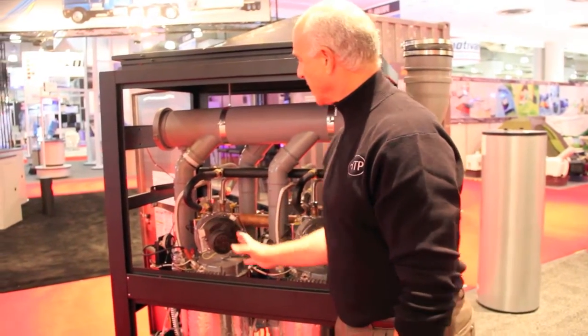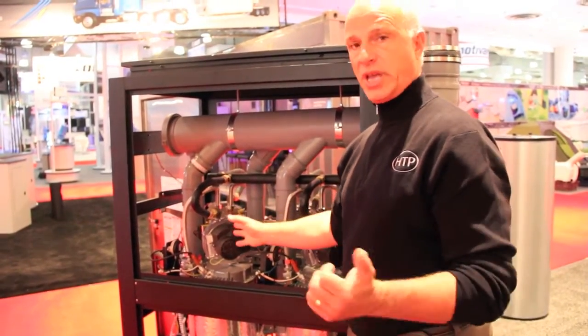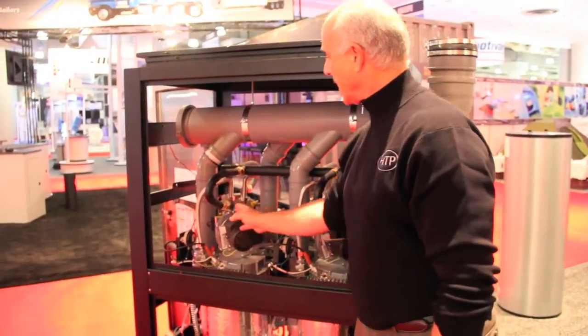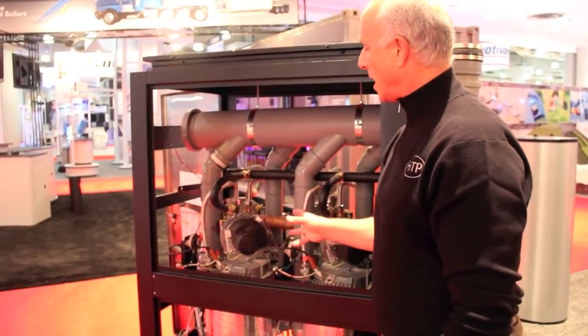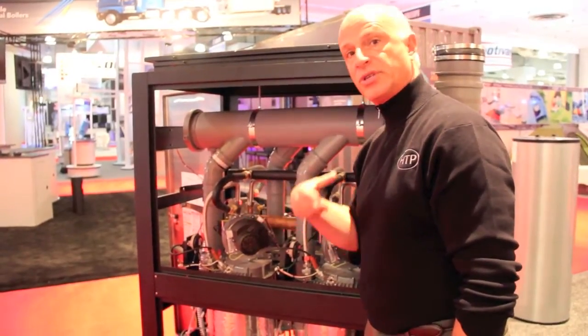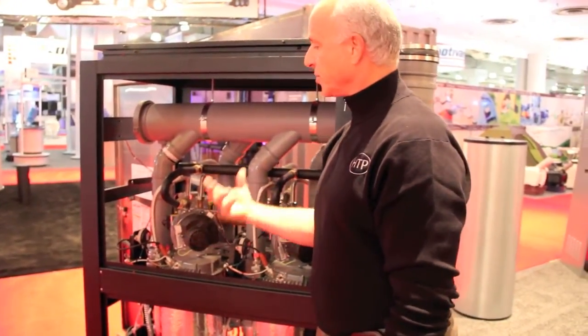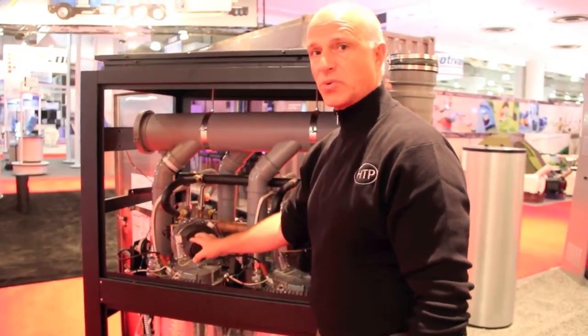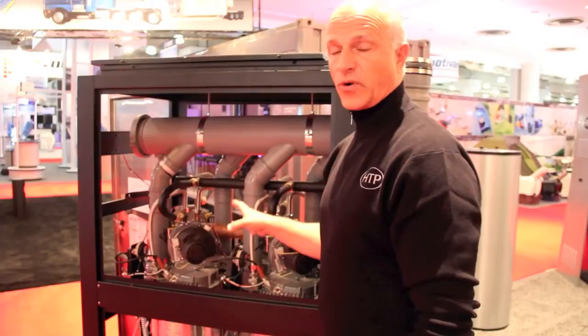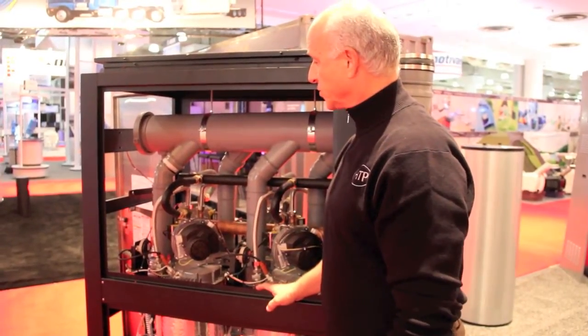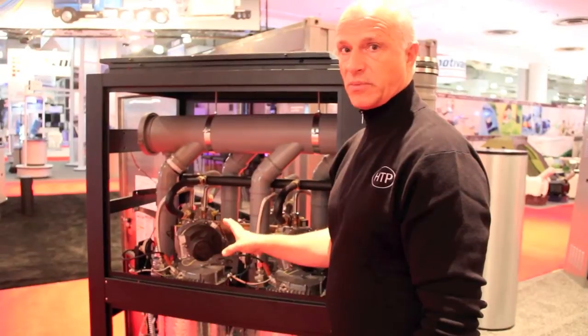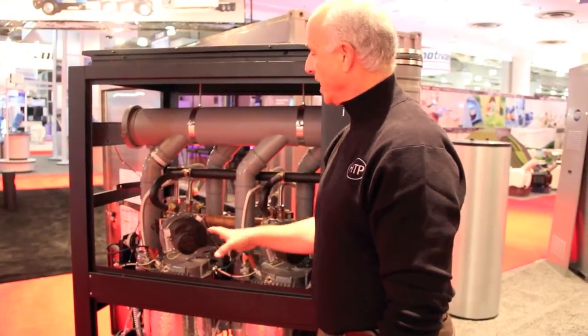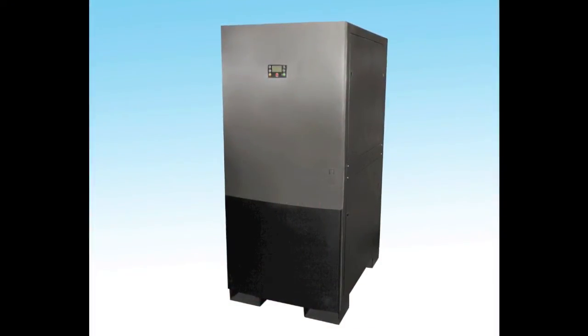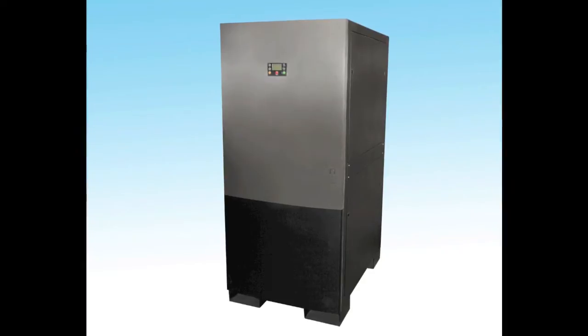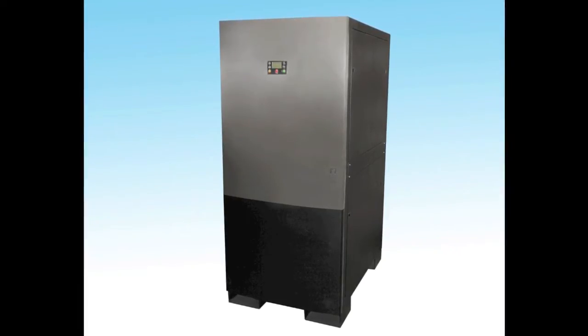So the operation of this, again, is the same type of situation that you have with the 250s. They'll independently operate, allow flow through it as we start to see an increase in demand. If you have recirc, again, it's only going to flow through probably one module instead of all four of them. It's really a unique product in the marketplace that'll allow customers not only to have the redundancy, which is a huge deal in today's market, but it'll really give you the very large turn down in a very compact size, and it'll give you very, very high performance.